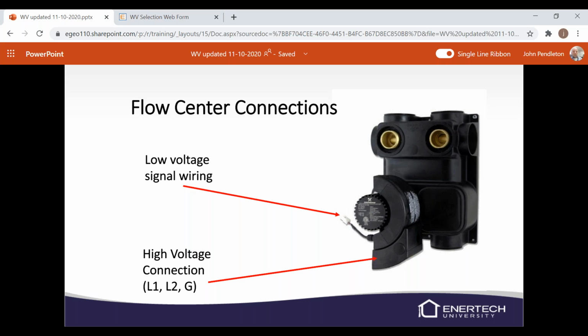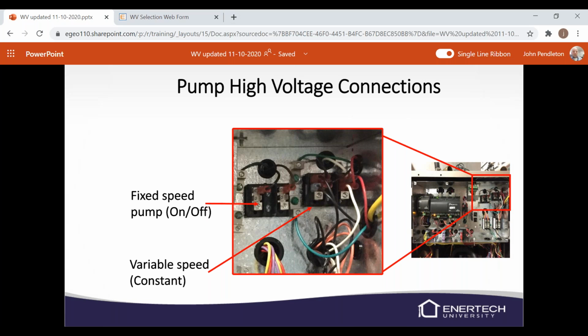The high voltage connections are located inside the pump, a little box there on the flow center itself. And again, these will be labeled. You have your fixed speed pump, so that's an on-off. The unit will decide when it sends 230 volts to that pump block. And then you have your variable speed power block, where that pump block has 230 volts all the time. A variable speed pump is similar to a variable speed ECM blower motor, where the motor has high voltage all the time, and the on-off or how it's controlled is based on the low voltage.